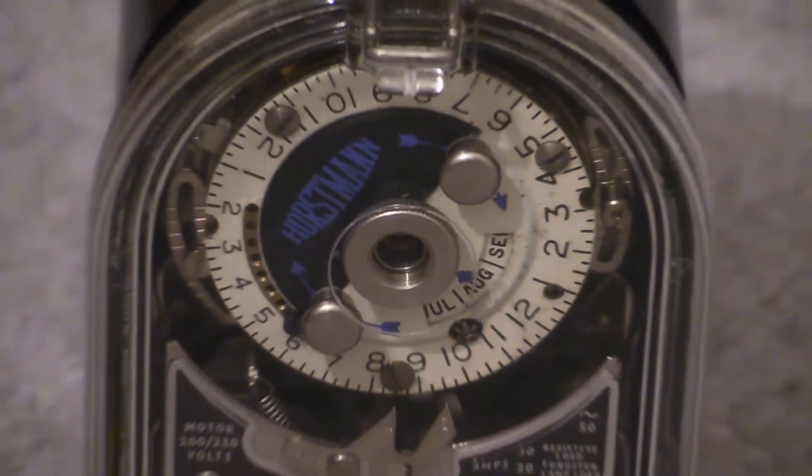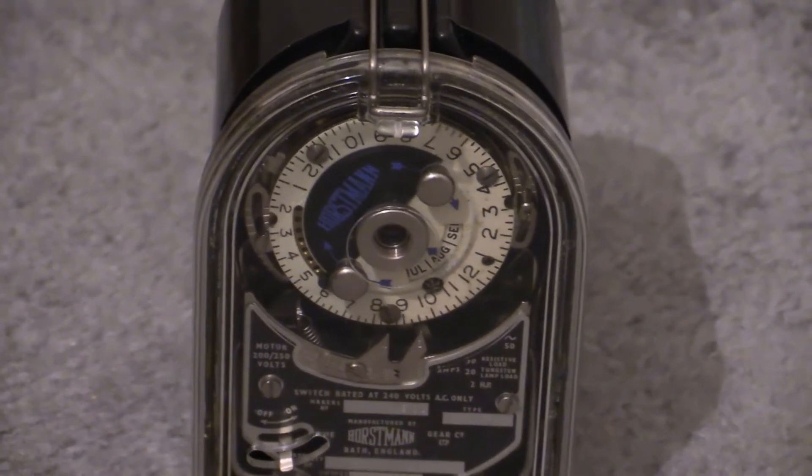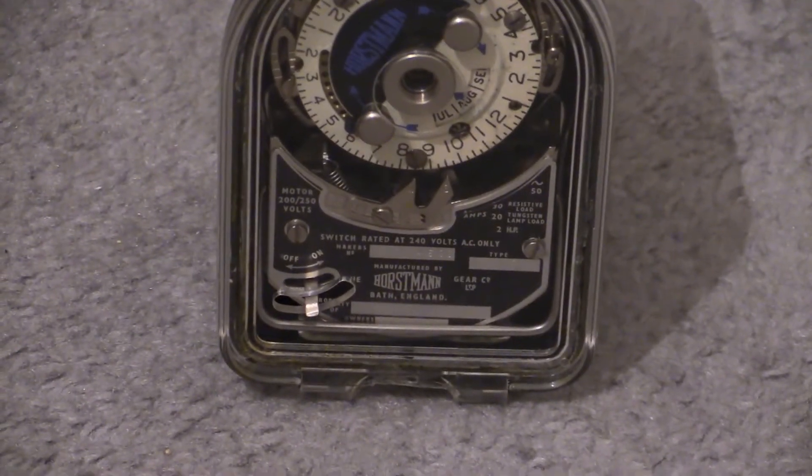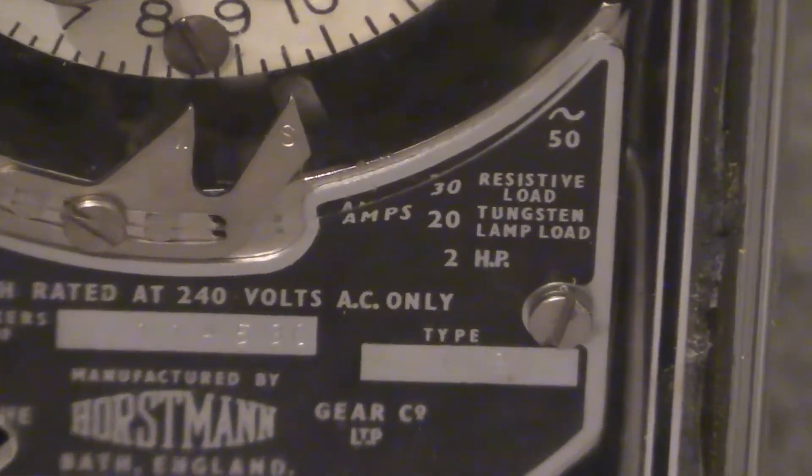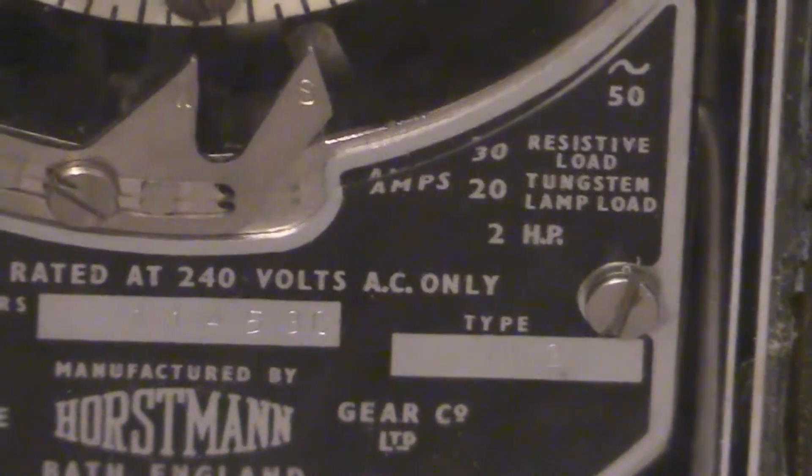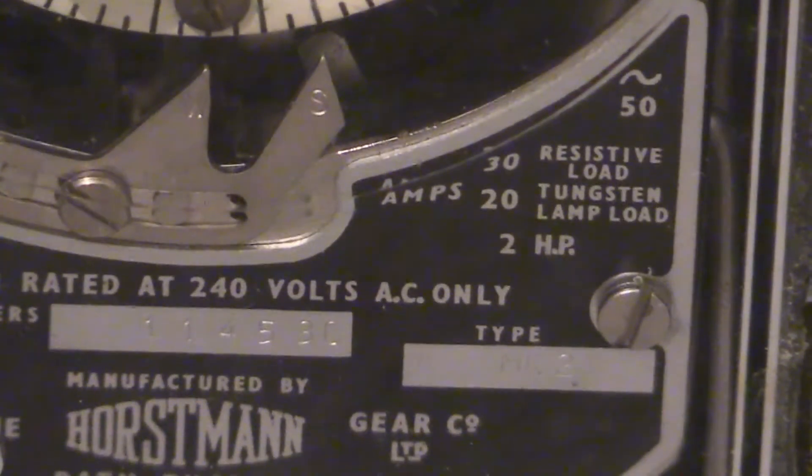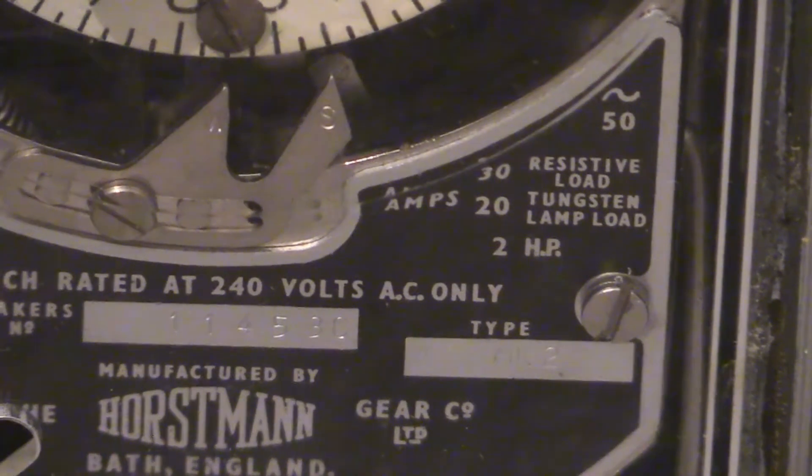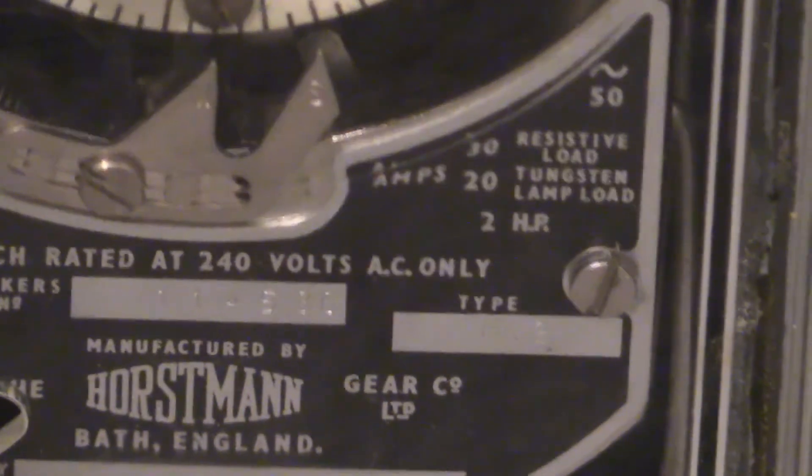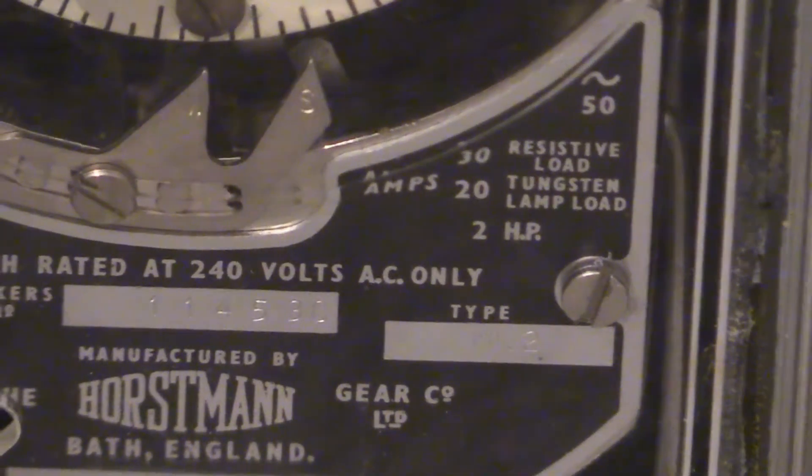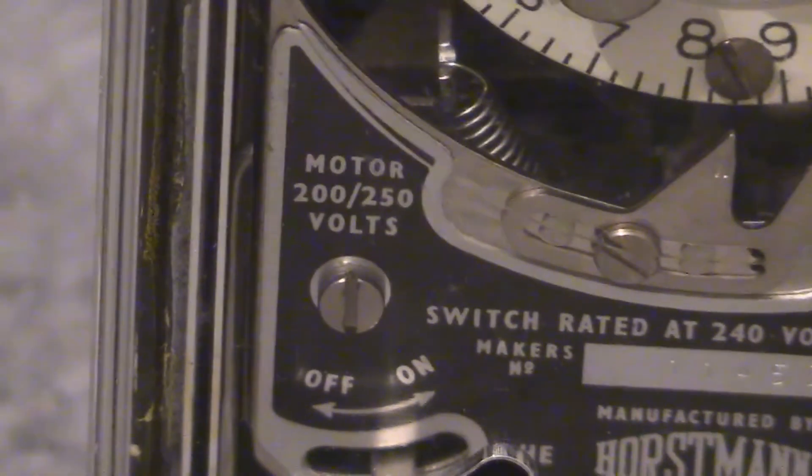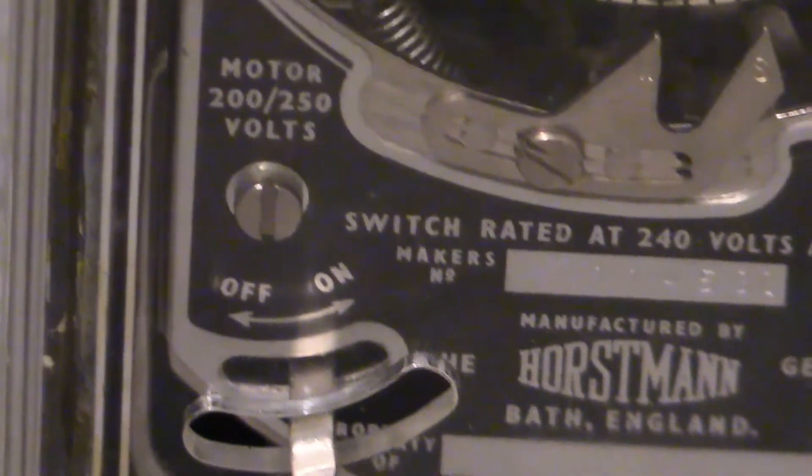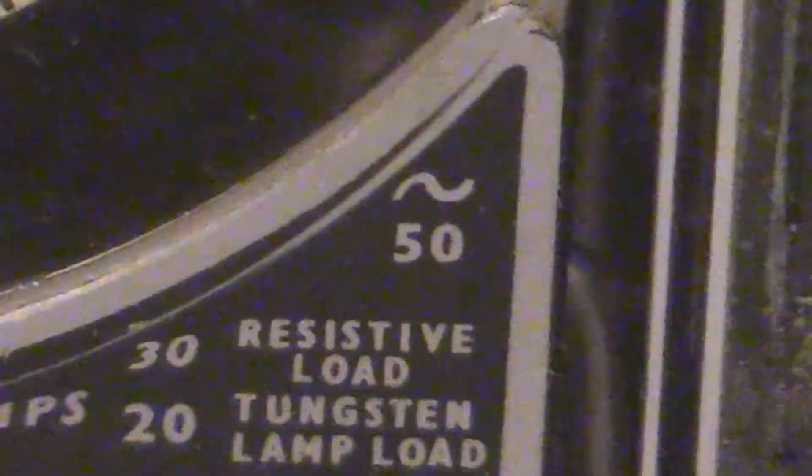Let's zoom in on the specification plate there and have a look at the characteristics for this one. This is a little basic model, and on the specifications it does make reference to resistive loads and lighting loads. Resistive load is 30 amps and tungsten lamp load is 20 amps, 240 volts for this, and the all-important 50 Hertz alternation frequency for the synchro motor. It says motor 200 to 250 volts, and I'm trying to see where on that specification plate it makes reference to 50 Hertz alternation frequency, and it is right there in that corner.